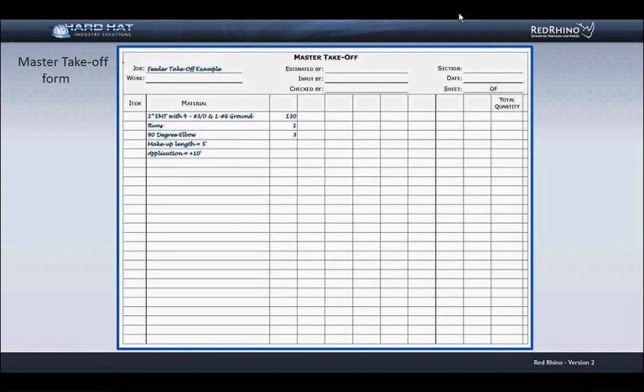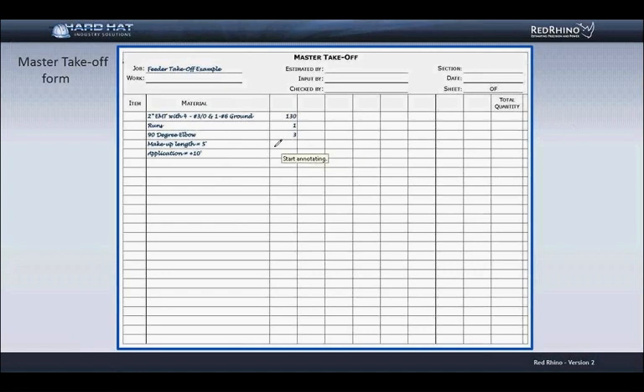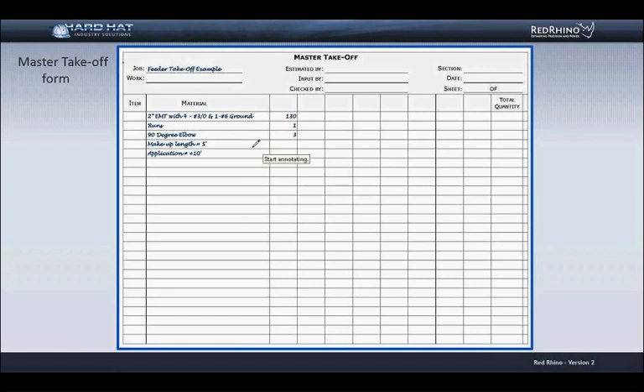Now I will define two other terms necessary for conduit takeoff. They are wire makeup and conduit application. Wire makeup is the length of additional wire that must be added for the wire to extend past the end of the conduit to the termination point. You must calculate the wire makeup length at both ends of the run and then average it. In our example, the conduit riser running out of the top of panel MSB I estimate requires 7 feet of makeup or wire makeup. In other words, I calculate it takes 7 feet of additional wire to extend the wire past the end of the conduit to the circuit breaker where the wire terminates at panel MSB.